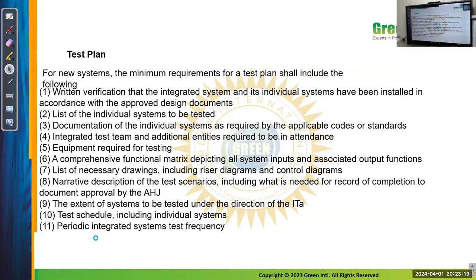So, test plan. The test plan will have the following checklist. For a new system, the minimum requirements for a test plan shall include the following: written verification that the integrated system and its individual systems have been installed in accordance with the approved design documents. This will not tell you whether the design is correct or not, but it will verify that it is as per the design, as we have seen in NFPA.